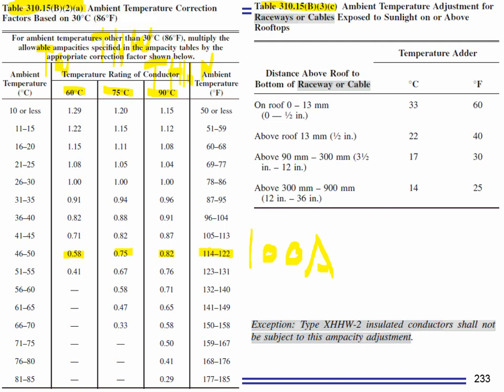Now, the second table next to it, guys, is for putting things on a roof. If you are putting conduits on the roof, your conduit will be cooked by three heating sources. One is by the current going through it. The second is by the sun beating on it. And the third is by the reflected heat from the roof. So they discovered that these conductors must be boiling down there. So now they want you to account for it. That came in 2011. How do you do it?